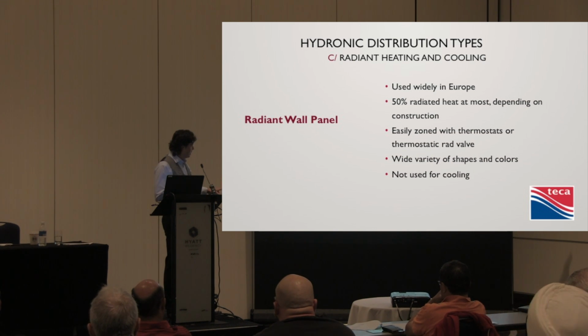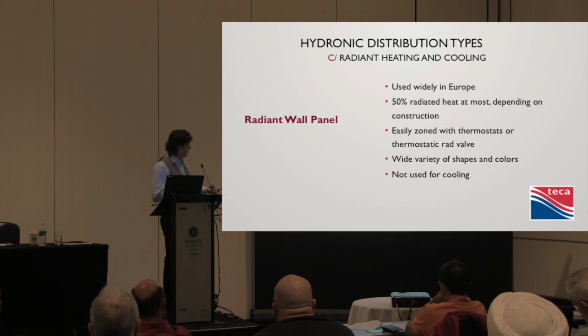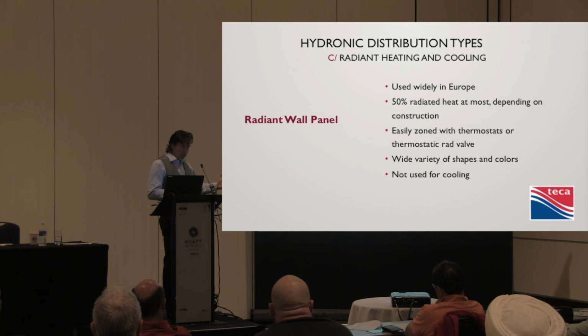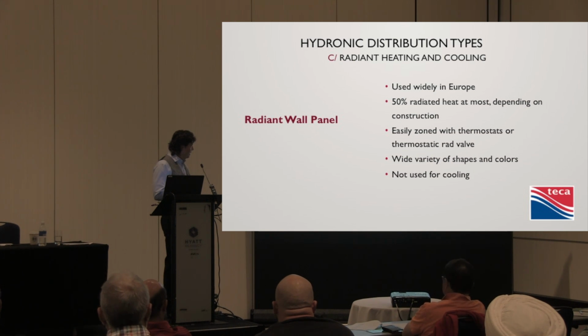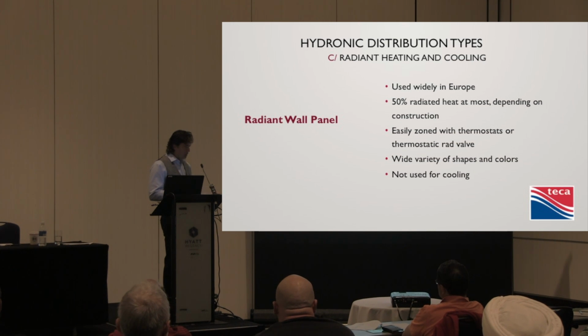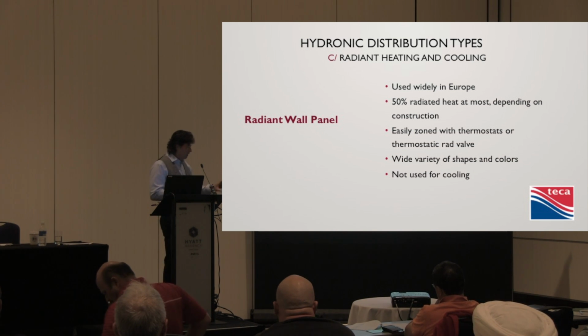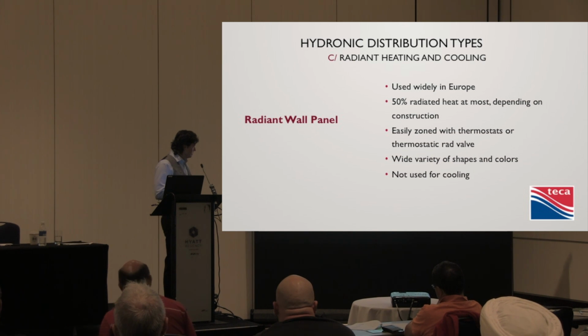These things use a lot lower temperatures, but it offers a more comfortable experience because a lot of the heat that comes off of that is a radiated style of heat. So it's warming your body and not the air, and you're not experiencing the air convective currents in the room. Easily zoned thermostats. You put a thermostat on the wall and connect it to a zone valve. You can have manifolds in a closet that go out to these things that are mounted on the walls. You can also use a local zone valve called a thermostatic valve. So, yeah, we wouldn't use them for cooling.